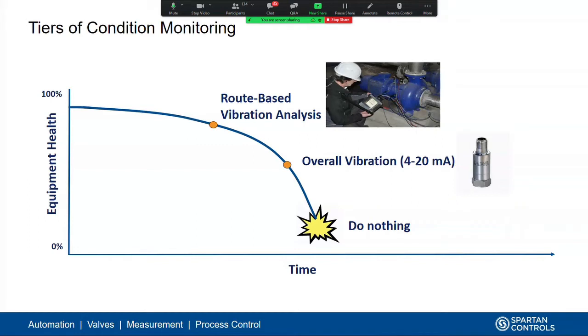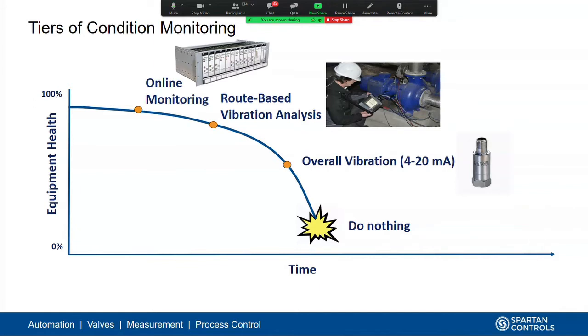So you need to make sure the frequency of your vibration analysis program is fast enough to actually detect and fix those failures. That's really the benefit an online condition monitoring system gives you. It basically gives you that analyst who would come out infrequently, say every few months, but an online monitoring system gives you that information immediately, second by second.